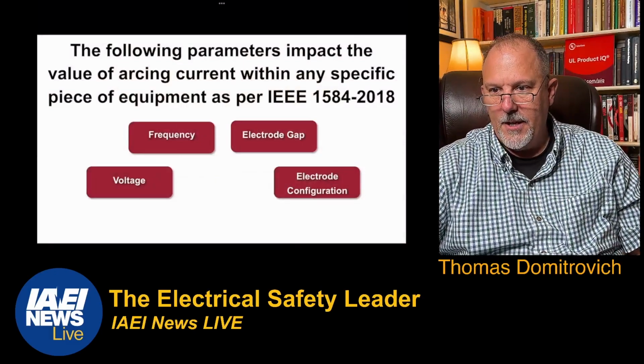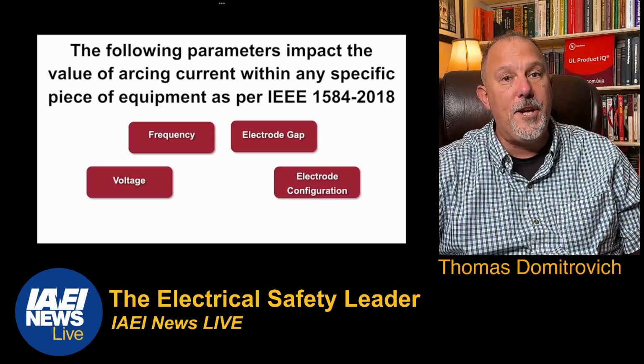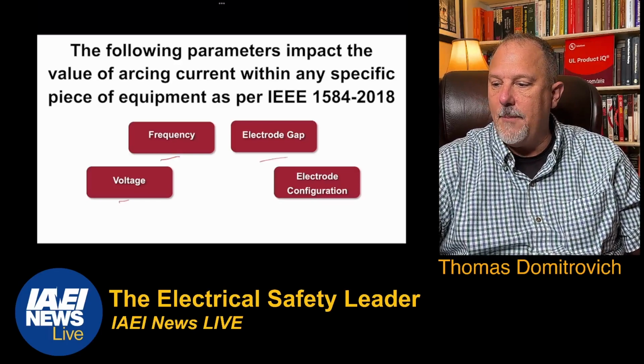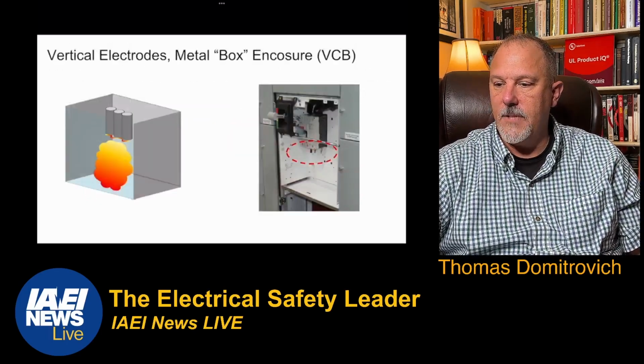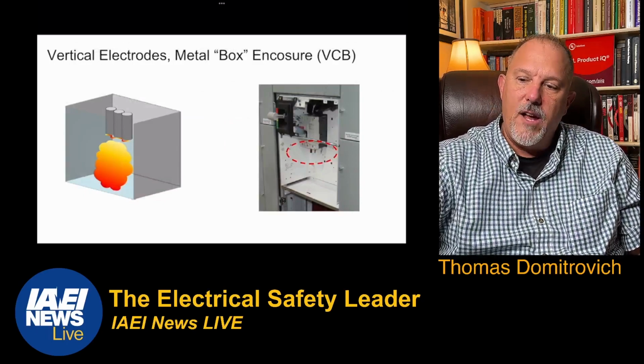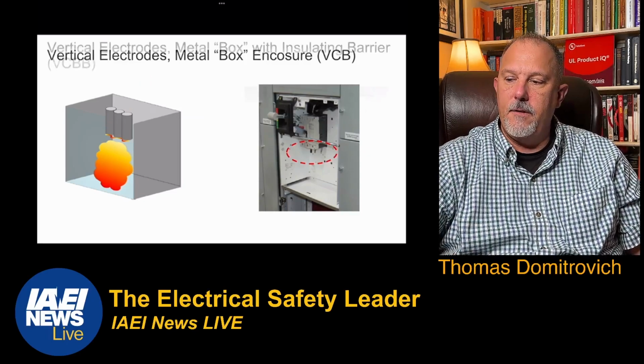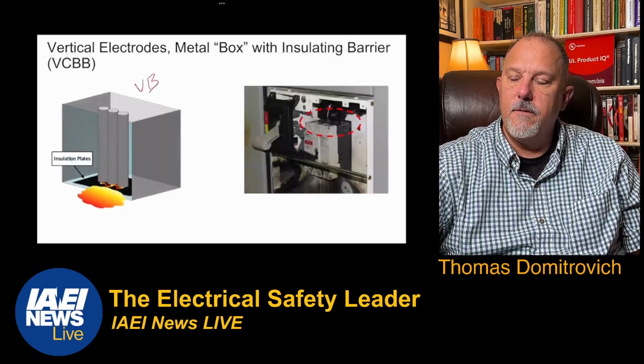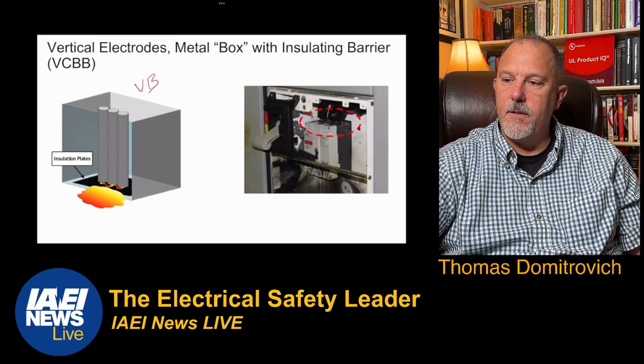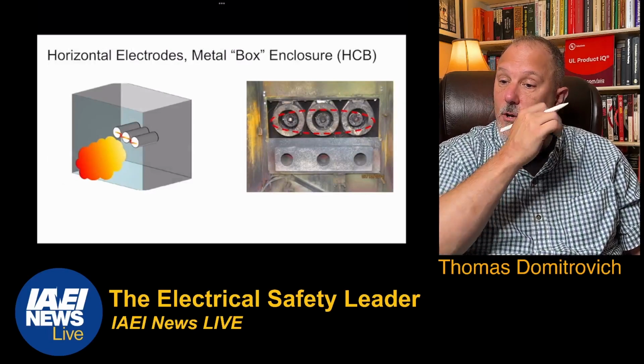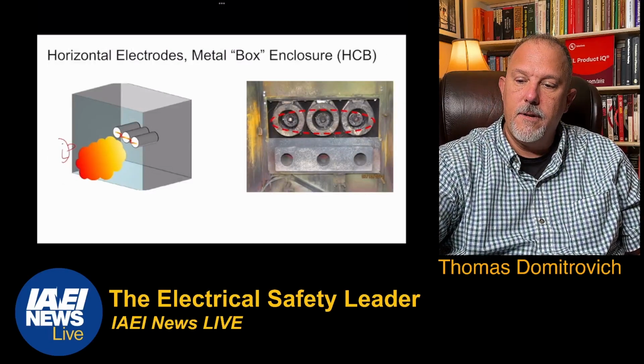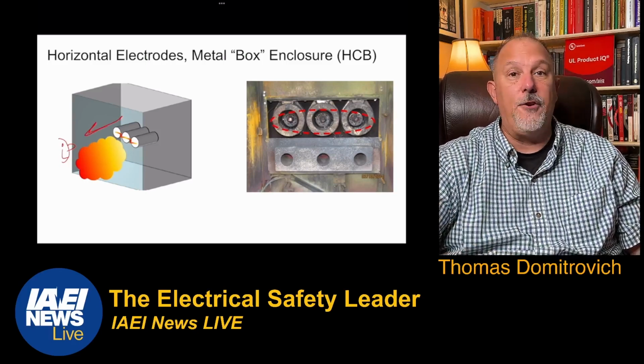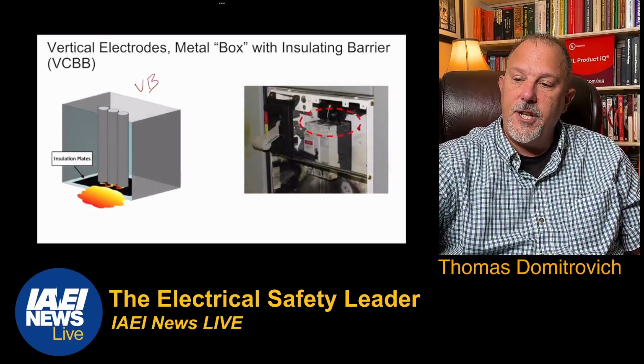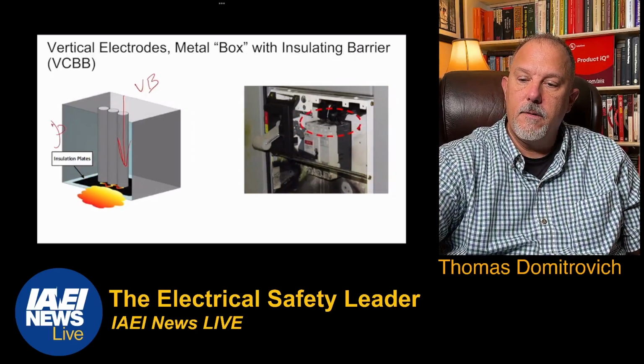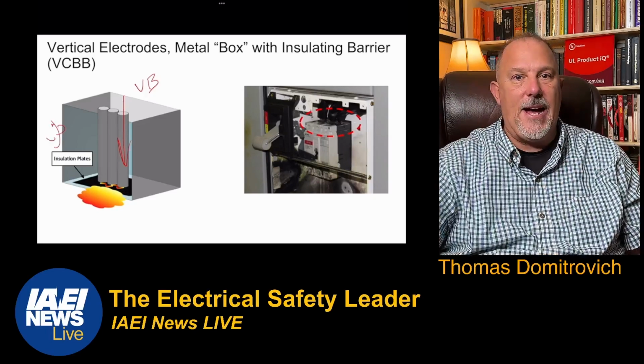So all of these parameters impact the arcing current. These are parameters that are in the equation for arcing current: frequency, voltage, electrode gap, electrode configuration. These are your different types of electrodes. Remember we said we have a vertical bus, and then this is a vertical bus with a barrier, and then we have a horizontal bus. So if you were sitting here facing it, the energy is coming directly at you like a freight train. In this case here, the energy is flowing and you're here. You're watching the freight train pass you, but then it hits the bottom and then bellows out towards you.